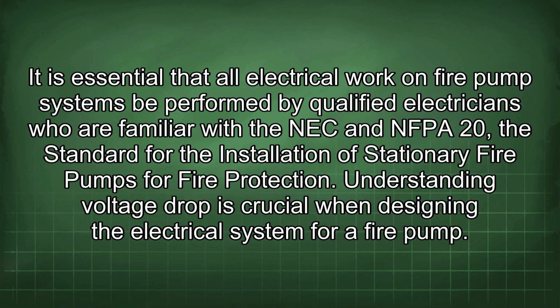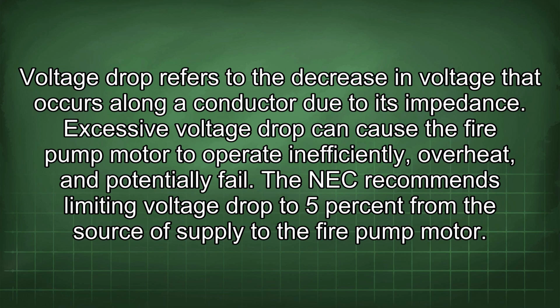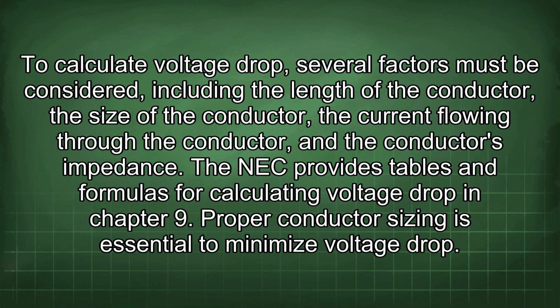Understanding voltage drop is crucial when designing the electrical system for a fire pump. Voltage drop refers to the decrease in voltage that occurs along a conductor due to its impedance. Excessive voltage drop can cause the fire pump motor to operate inefficiently, overheat, and potentially fail. The NEC recommends limiting voltage drop to 5% from the source of supply to the fire pump motor. To calculate voltage drop, several factors must be considered, including the length of the conductor, the size of the conductor, the current flowing through the conductor, and the conductor's impedance. The NEC provides tables and formulas for calculating voltage drop in Chapter 9.